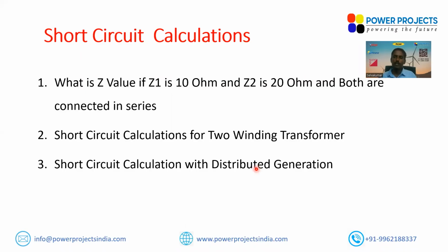For the distributed generation, we need to ask whether it is inverter based, like solar inverters, or machine based, like biomass. So you need to be a bit careful. In a recent project we are working on, the EPC has backed the order. The wind farm was a Type 4 full converter based wind turbine generator, and they have done the sizing calculation based on that, and they have backed the order.